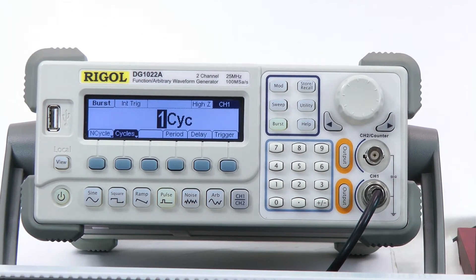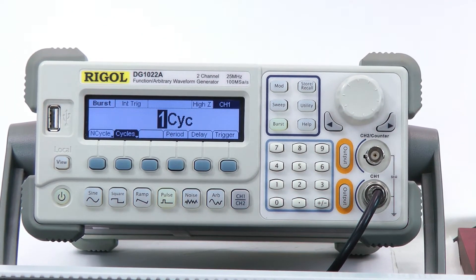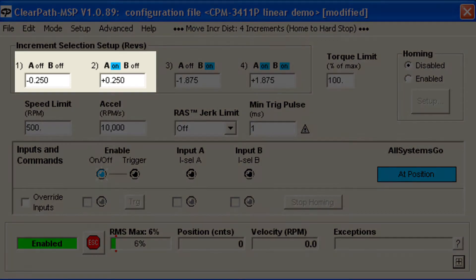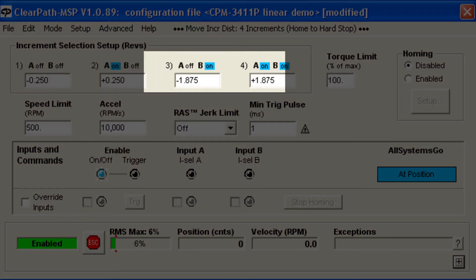Most people for this mode use programmable digital outputs, like from a PLC. Most applications travel bidirectionally, and in these cases you'll want to enter both positive and negative increments — one relatively small value and one larger value for each direction. You'll see why in a moment.